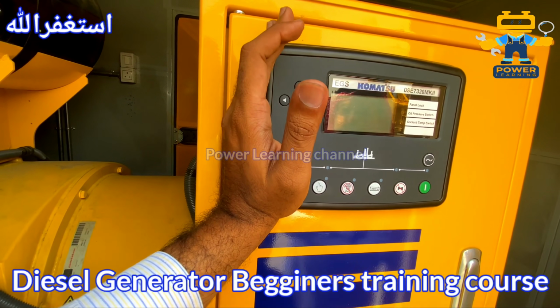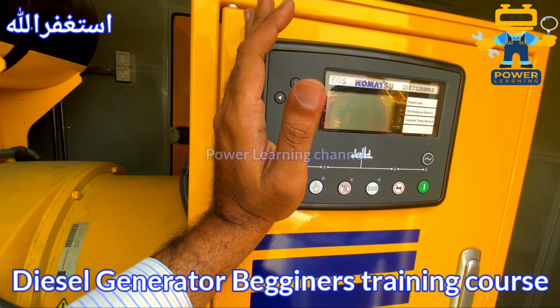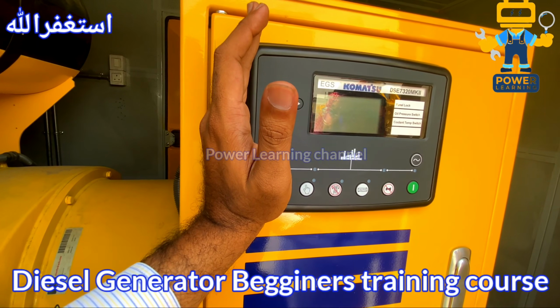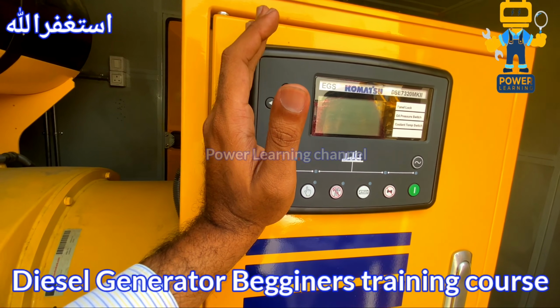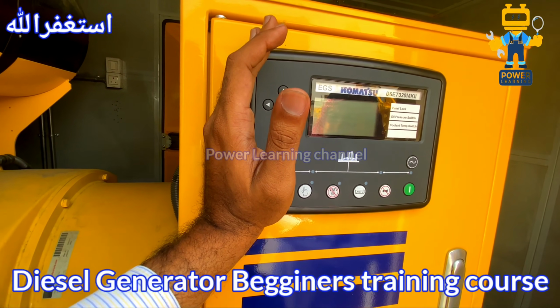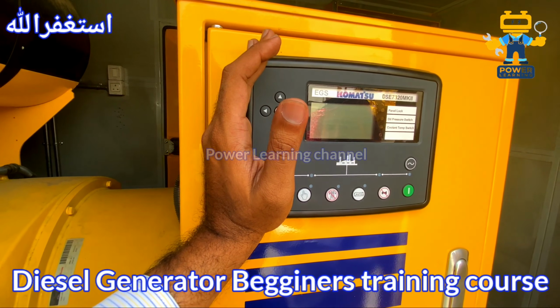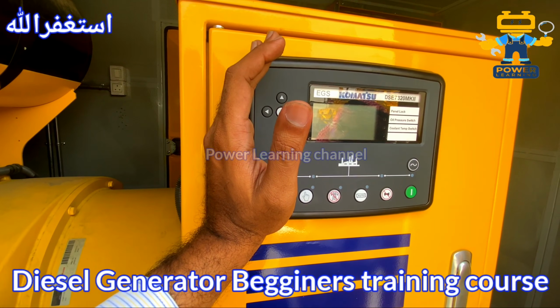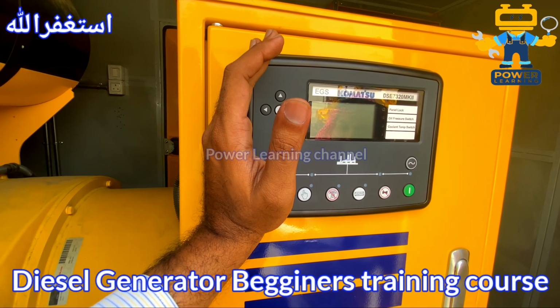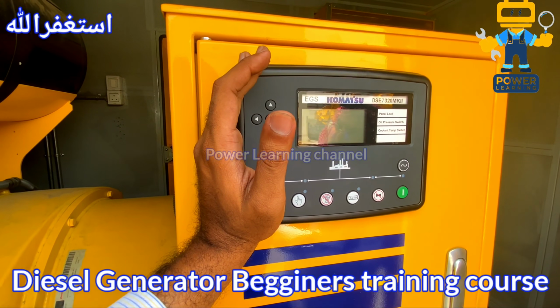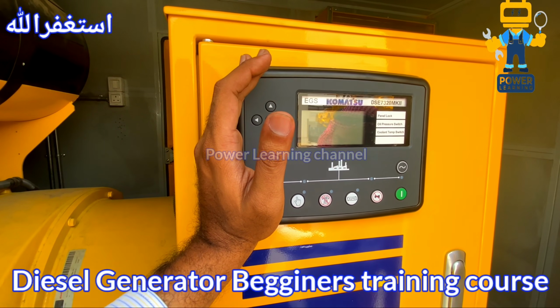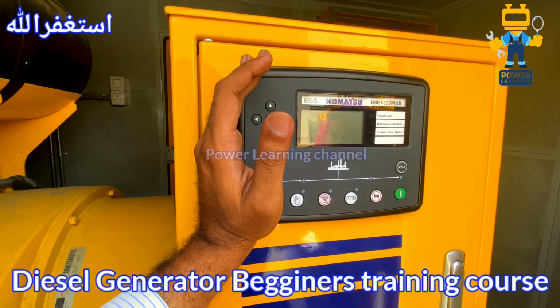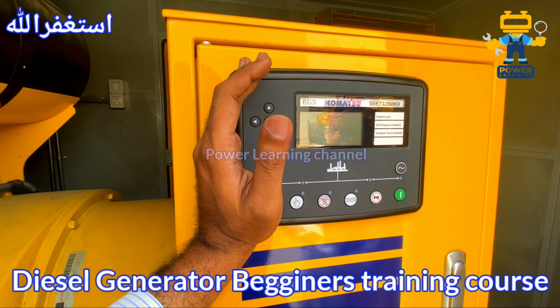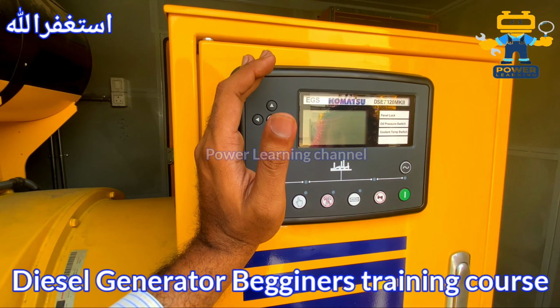From the set point, it will automatically turn off the engine. Or whenever the nominal settings of our generator are not reached, it will also turn off the engine. When all the values are normal, it will keep running our generator. For example, if the voltage increases beyond our set level, it will turn off the engine. If voltage decreases below our set level, it will also turn off the engine.